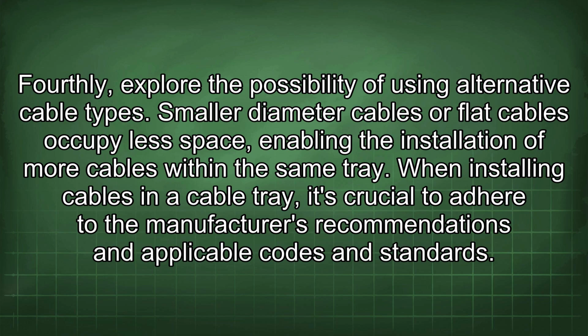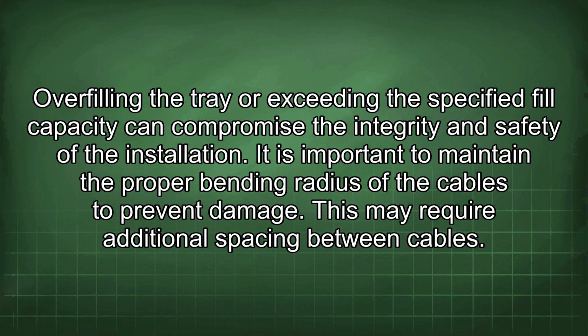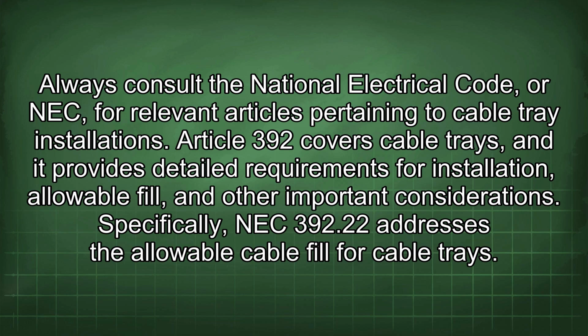When installing cables in a cable tray, it's crucial to adhere to the manufacturer's recommendations and applicable codes and standards. Overfilling the tray or exceeding the specified fill capacity can compromise the integrity and safety of the installation. It is important to maintain the proper bending radius of the cables to prevent damage. This may require additional spacing between cables. Always consult the National Electrical Code, or NEC, for relevant articles pertaining to cable tray installations. Article 392 covers cable trays, and it provides detailed requirements for installation, allowable fill, and other important considerations.